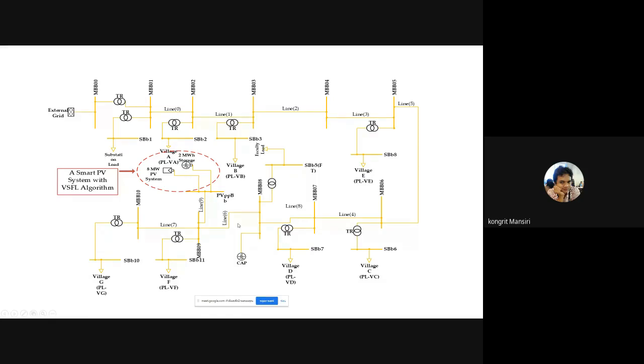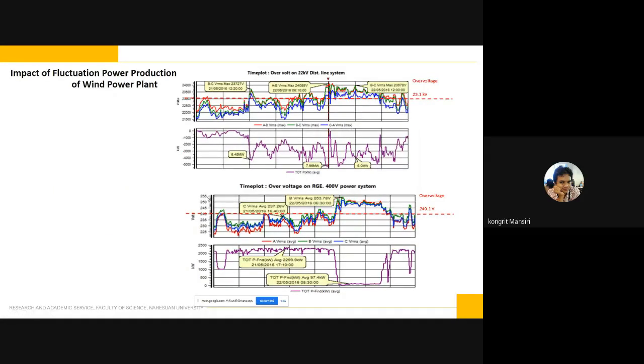When there is high solar irradiation, the active power is injected into the grid, and the voltage fluctuates, sometimes over the limit of PEA. This is from the real data of the power plant. When there is high active power injected into the grid, the voltage increases over the limit of PEA, because normally our distribution is 22 kV, but this becomes 23.1 kV, so it's over. When it's over, they have to disconnect from the grid, and that causes voltage fluctuations.